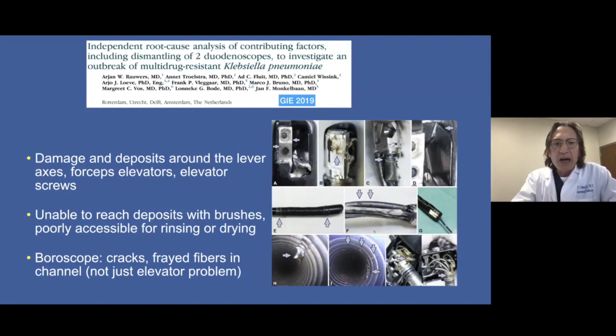And when you look into the working channel, that's where you see where I think the real problem is, aside from the elevator, and that is all the cracks, the fraying, the disintegration of the lining that occurs over repeat uses. It really looks like a war zone when you look inside of the working channel. So next time you pass your spyglass probe through your duodenoscope, take time and look at the lining of the working channel. I did, and it is really quite daunting.